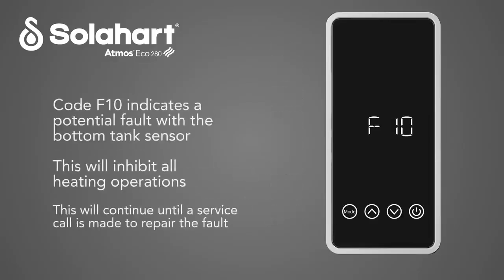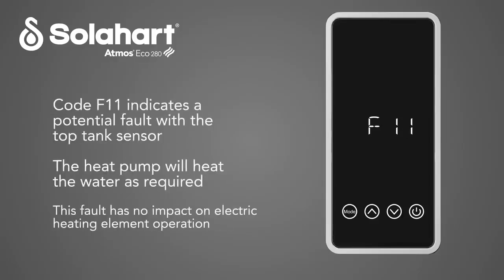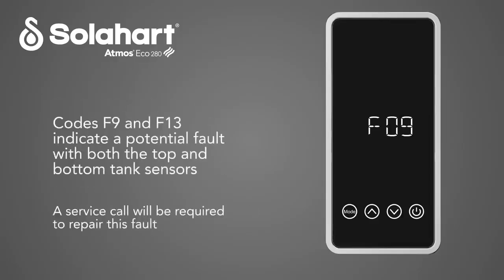Code F10 indicates a potential fault with bottom tank sensor. This will inhibit all heating operations. Code F11 indicates a potential fault with top tank sensor. The heat pump will heat the water as required. This fault has no impact on electric heating element operation. Codes F9 and F13 indicate a potential fault with both the top and bottom tank sensors.